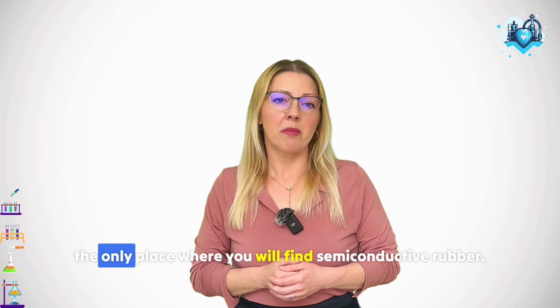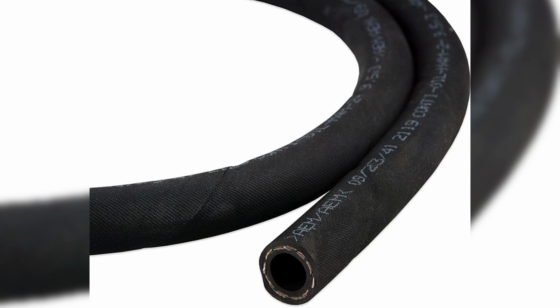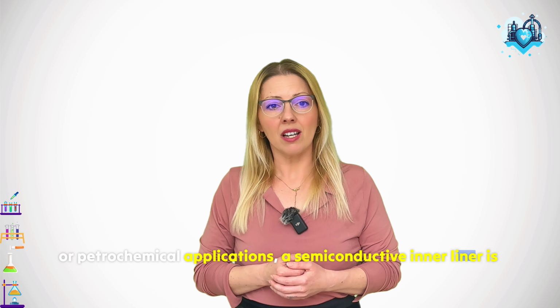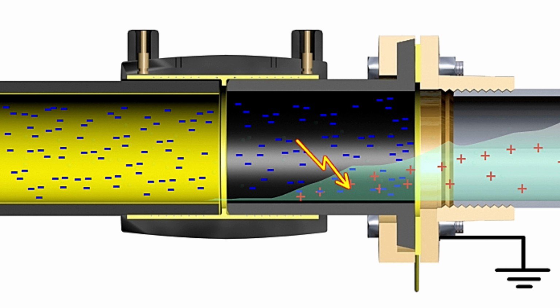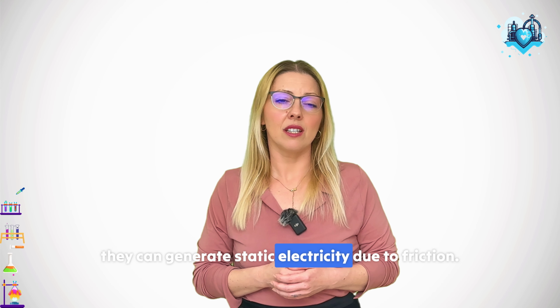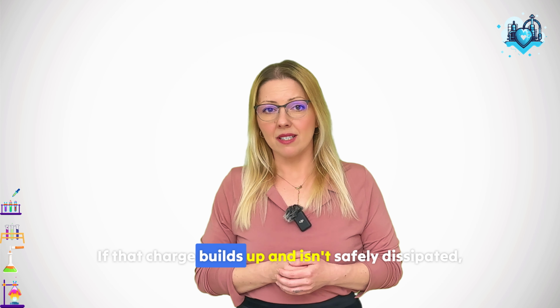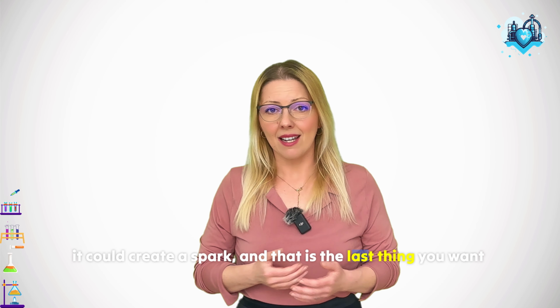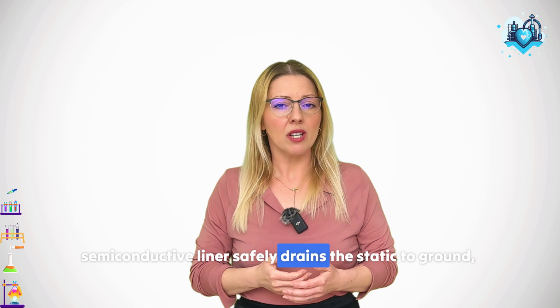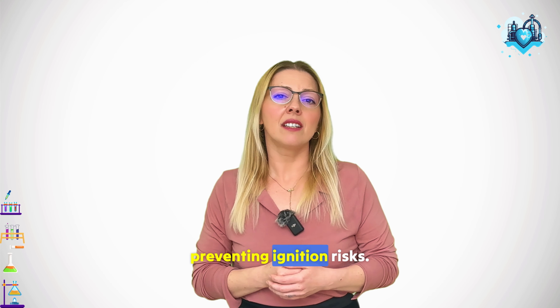But that is not the only place where you will find semiconductive rubber. In fuel and oil hoses, especially in aviation or petrochemical applications, a semiconductive inner liner is critical for static discharge protection. As fluids like gasoline or jet fuel flow through a hose, they can generate static electricity due to friction. If that charge builds up and isn't safely dissipated, it could create a spark, and that is the last thing you want around flammable vapors. The semiconductive liner safely drains the static to ground, preventing ignition risks.